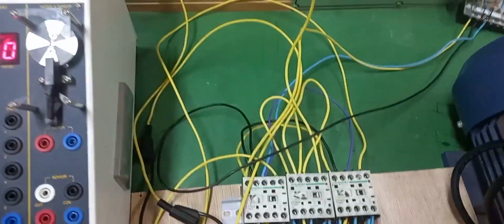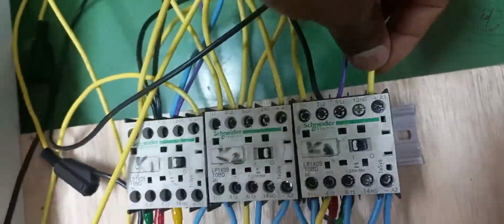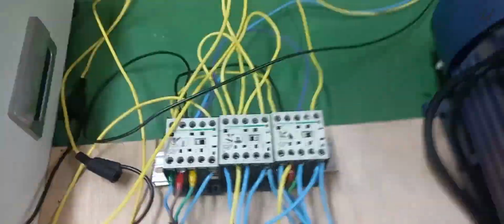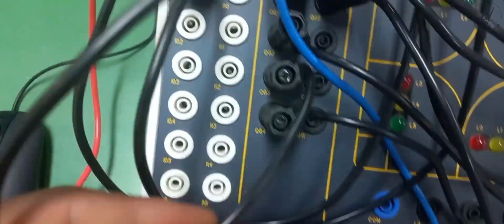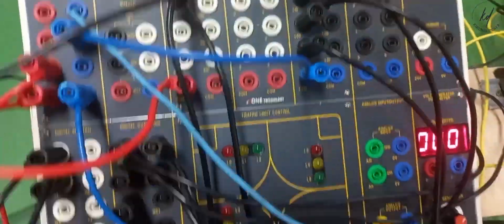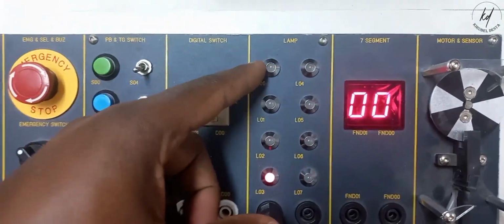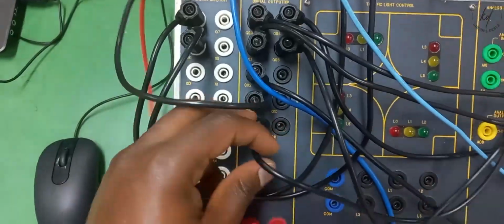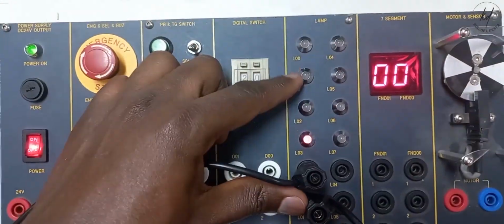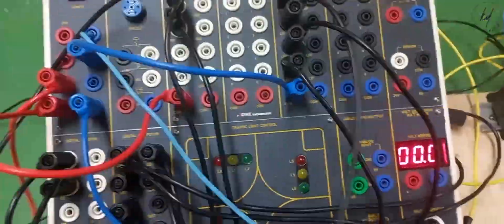Third, open state. This state is the transition state from star to delta. The main contactor is closed, while both the star and delta contactors are open. There is a voltage across only one end of the motor windings. The rotor is still rotating. Fourth, delta state. The main and delta contactors are closed and the star contactor is open. The motor is running with full line voltage and full load speed.